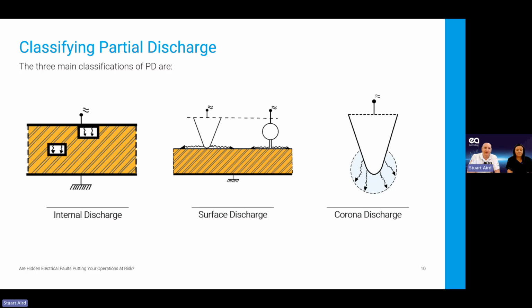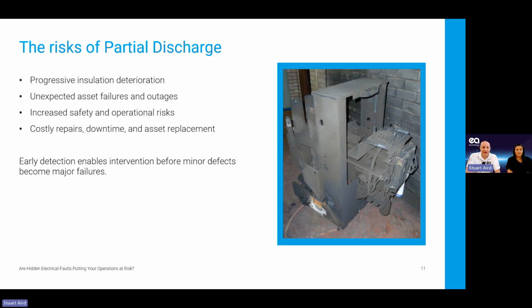There are a few intermediate partial discharges, things like gap discharges, that we can see in the field as well. But these are the three primary types that we're focused on while we're testing with our instruments. Ultimately, these will lead to progressive failure. So we want to be detecting partial discharge in our surveys and in our switchgear types, and we're going to try and prevent these unexpected asset failures so that hopefully we can increase safety. We're all working in these substations on a regular basis. We hope that we're as safe as we possibly can be. It's never a completely safe environment, but if we go in and take partial discharge measurements, we can make ourselves feel a little bit safer in there.